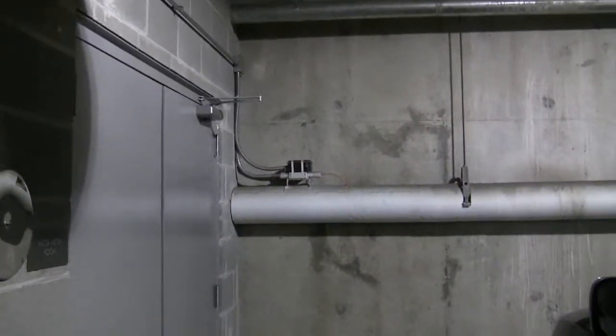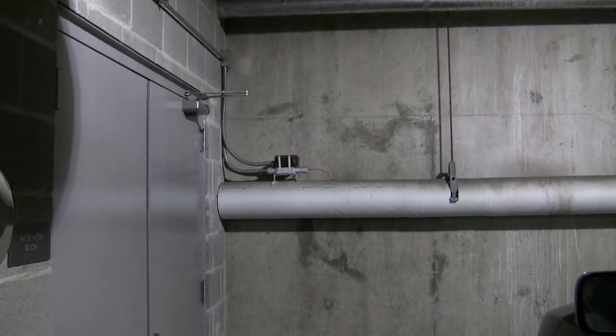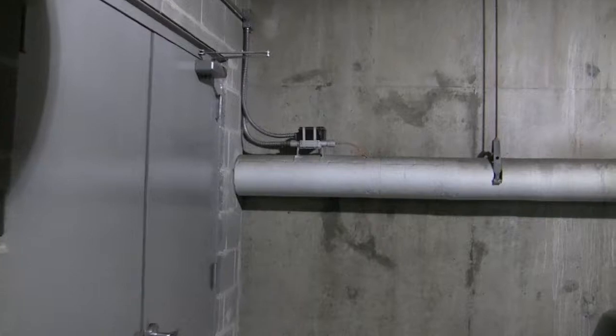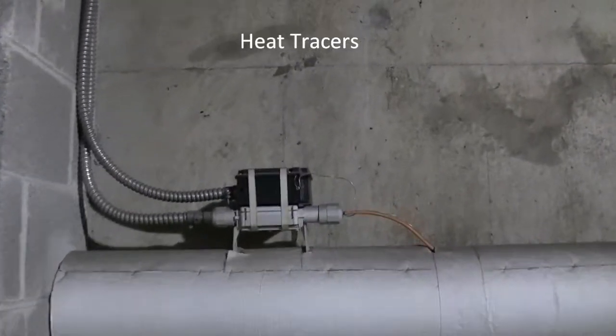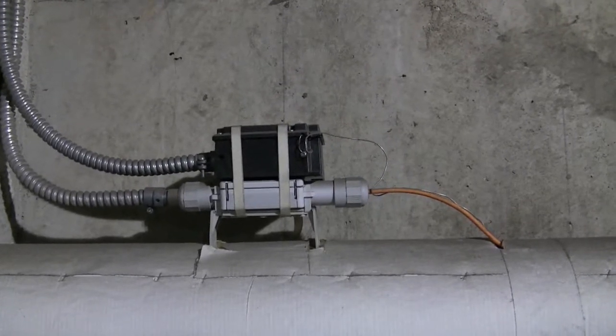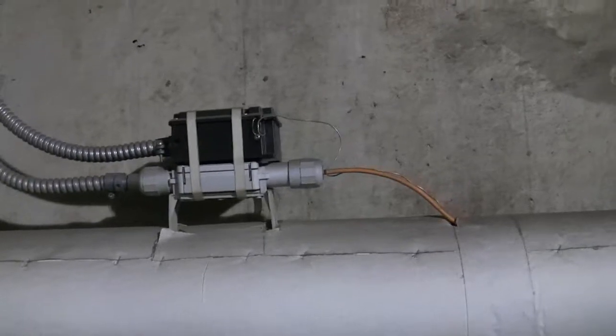And you said this is a double system, one is redundant? No, I didn't. What you have here is a medium pressure inlet, which is a very small pipe, and medium pressure comes in, goes through two governors to reduce pressure, and then takes a much larger pipe to discharge through the building at a lower pressure. Okay. Further, many of these lines carry heat traces in them, to prevent freeze-ups, and that is a typical heat trace thermostat. Okay, is this right on the panel upstairs? It goes back to one of the panels, yes. Okay, we'll get to that in a bit.